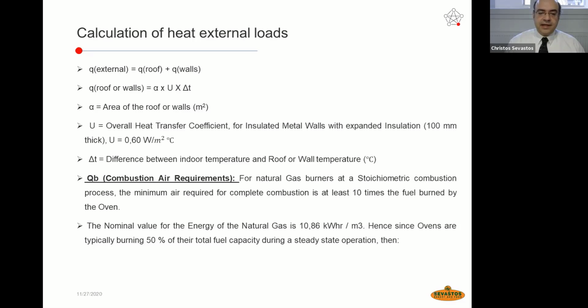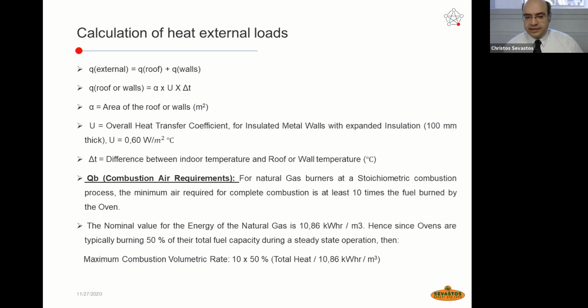The nominal value for the energy of natural gas is 10.86 kilowatt-hour per cubic meter. Ovens are typically, as we have said, burning 50% of their total fuel capacity during steady state operation. So the maximum combustion volumetric rate to the burners would be 10 times 50% of the total heat divided by the energy rate, the nominal value of the energy of the natural gas. We are going to refer to an example of the calculations needed in order to define the air ventilation.